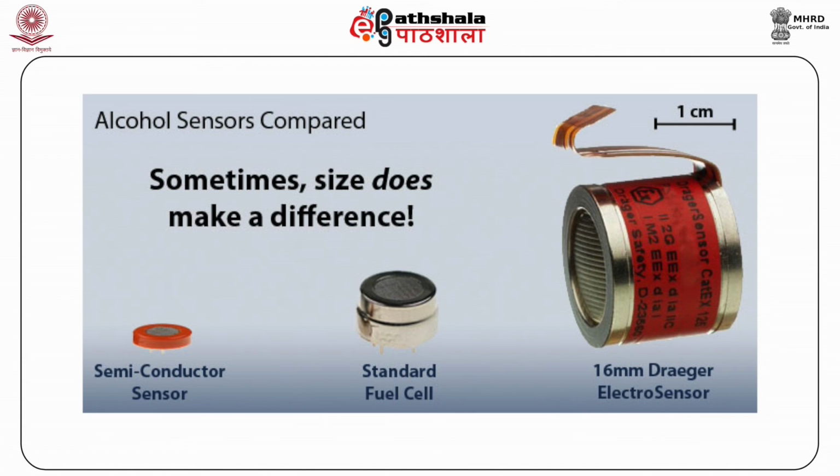These sensors are way ahead in their susceptibility to interfering substances and are prone to contamination by substances other than breath alcohol. Such sensors thus require replacement or recalibration at regular intervals.